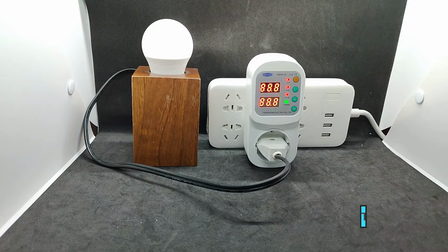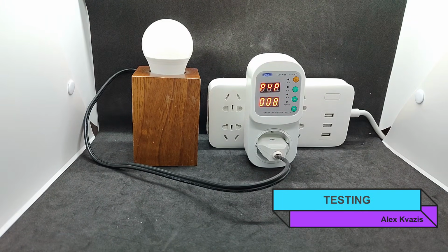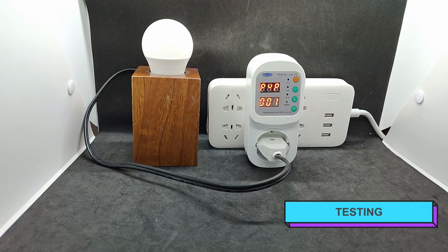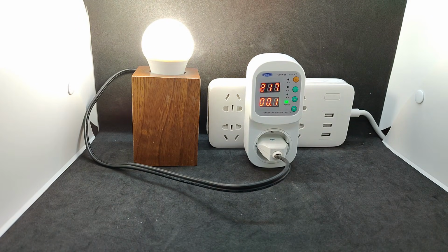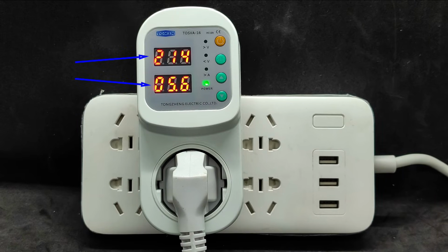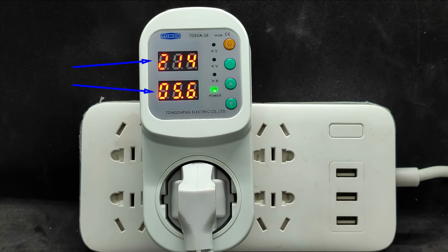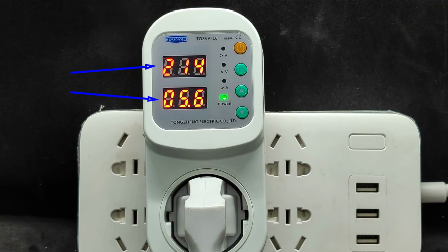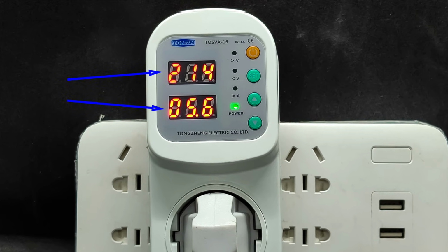When power is applied, a timer is activated, which can be set in the range from 1 to 500 seconds, with the default being 10. This makes it possible to separate and time the switching on of high-power loads so that there is no simultaneous surge. In standard operating mode, the upper digital display shows the current voltage, and the lower one shows the current.